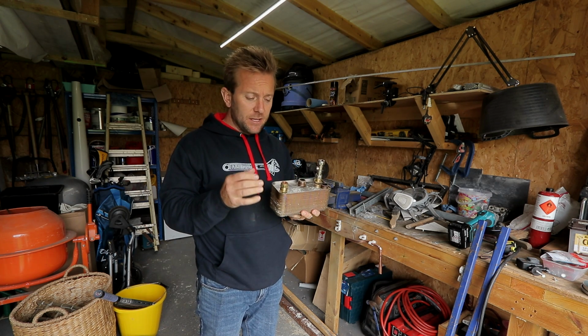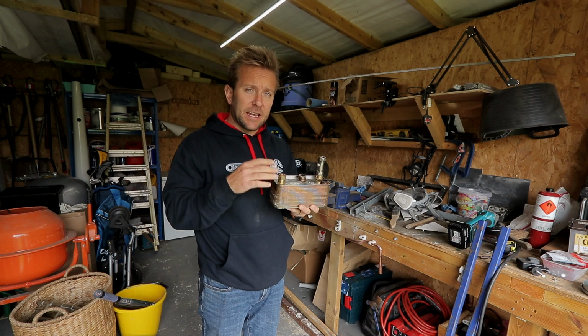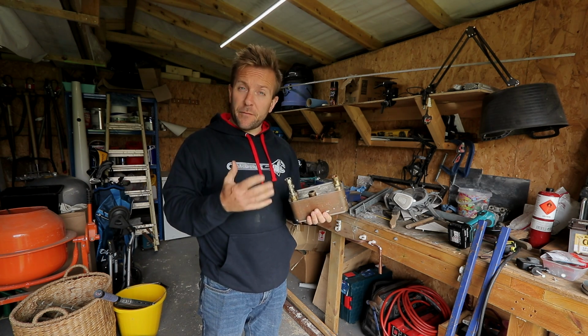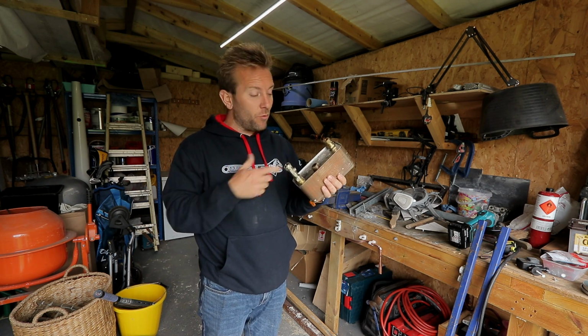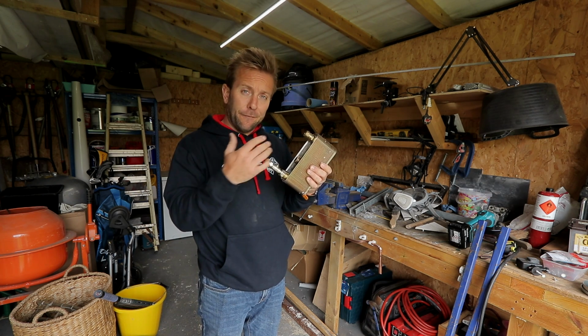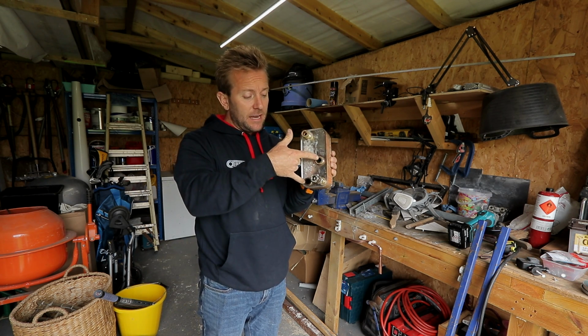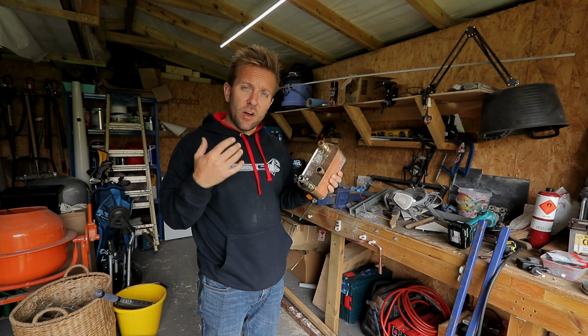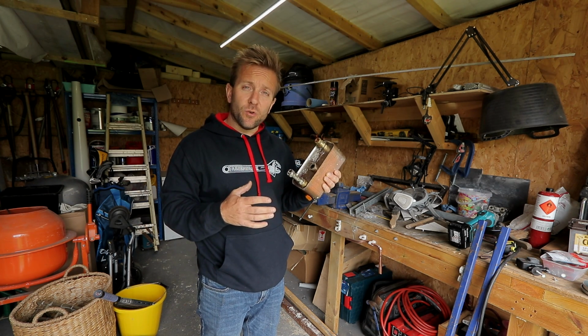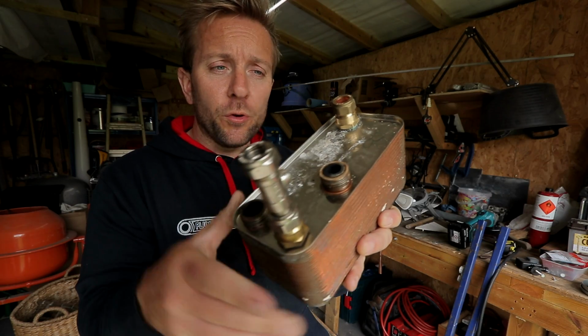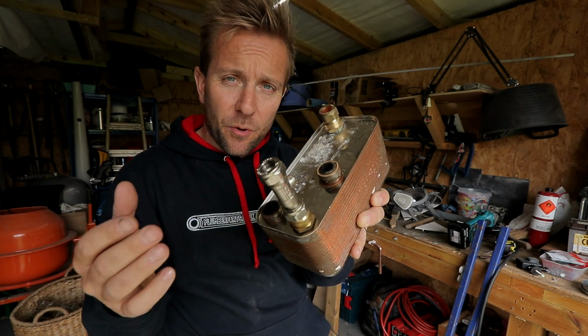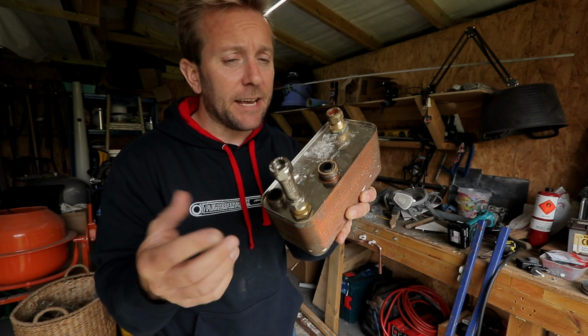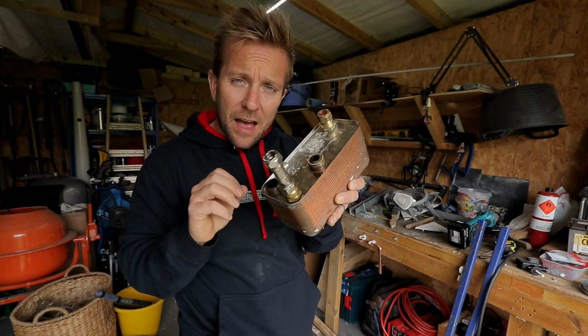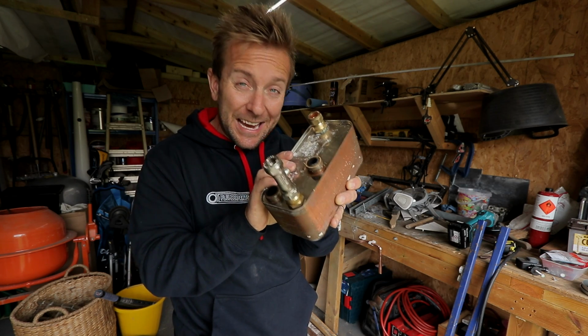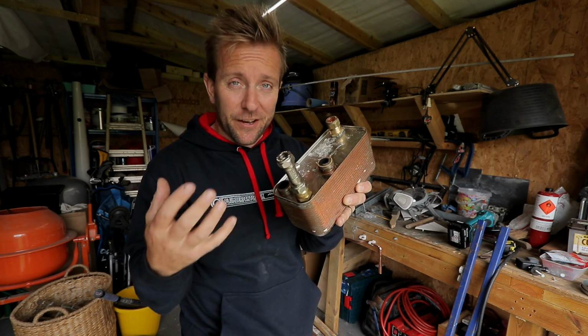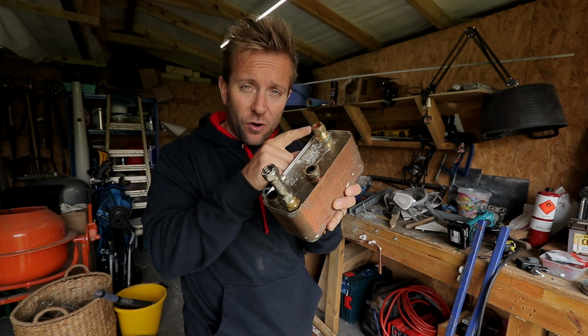What I'm going to do is pressurise the cold feed and the hot side. But before that, let me tell you what these pipes are for. We've got our flow and return from our heating system - that's heated water from the boiler that doesn't mix at all with the hot water from your taps, and it flows through here and back to the boiler to be reheated as needed. We've got our cold feed in, and that picks up heat in a transfer, which is exactly what the heat exchanger does - it exchanges heat, transfers heat, and that picks up and goes out to the hot taps.